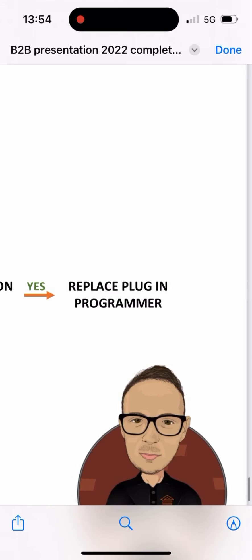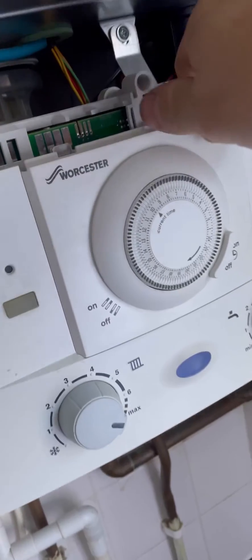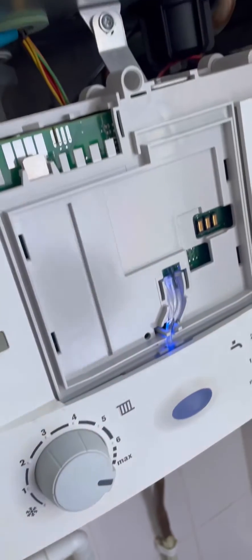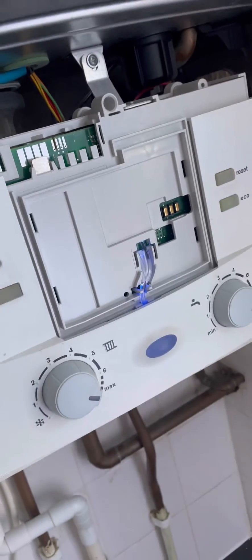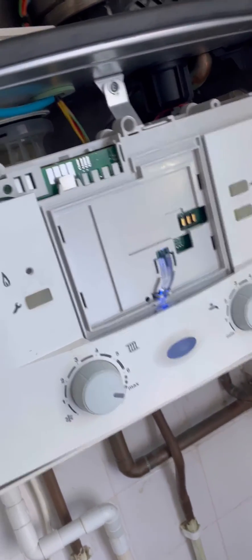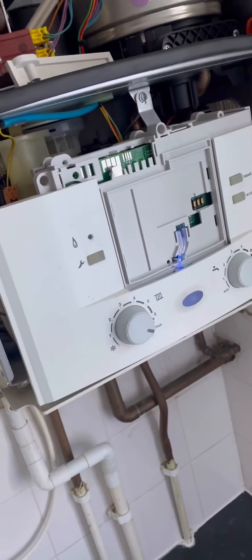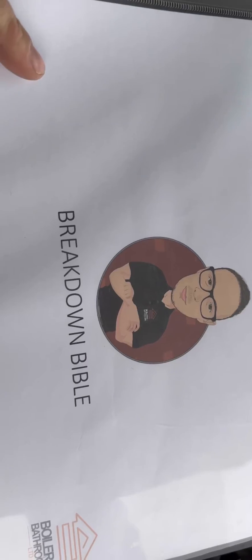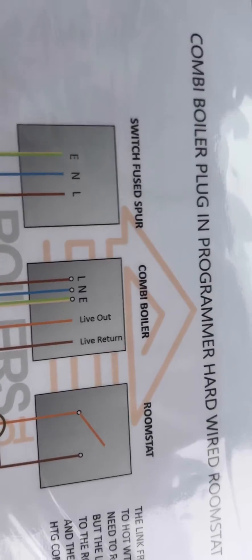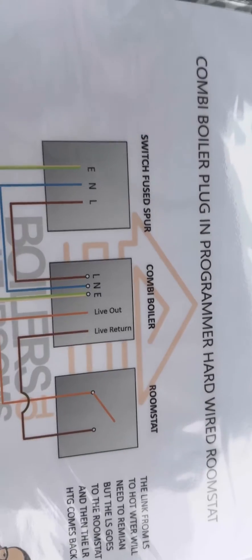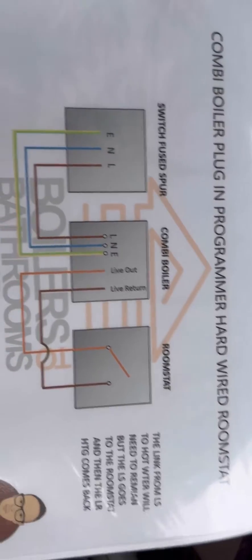So we replace the plug-in programmer, whip that out, boiler fires - happy days. It's a combi boiler, plug-in programmer, hardwired room stat.